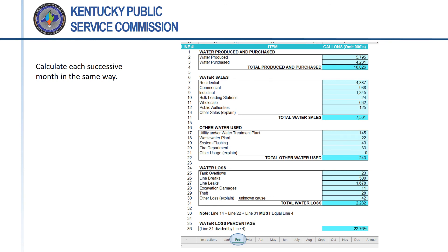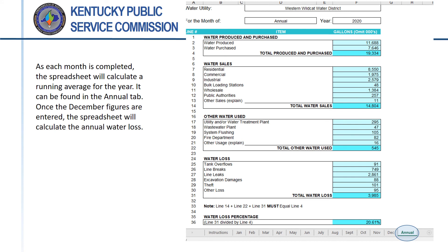Each month should be calculated in the same way — do not simply enter the same numbers for each month. Keep in mind that utilities are required to maintain true and accurate records, and that all records are subject to review by the PSC. As the data for each month are entered, the form will calculate a running total for each line item and will calculate the water loss for the year to date. The total water loss will be calculated from the cumulative totals for water produced or purchased, water sold, non-revenue authorized use, and water loss — it will not be a simple average of the monthly percentages.